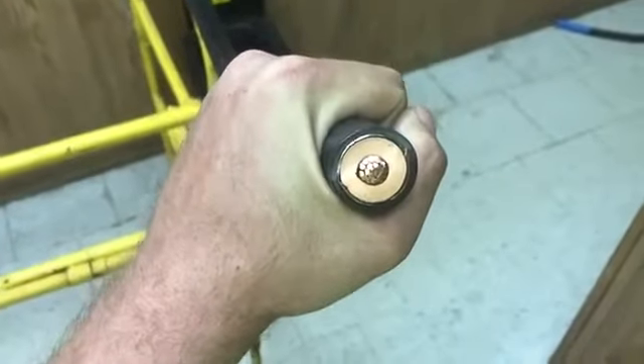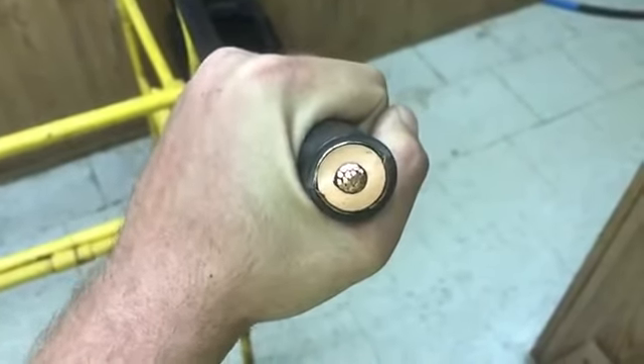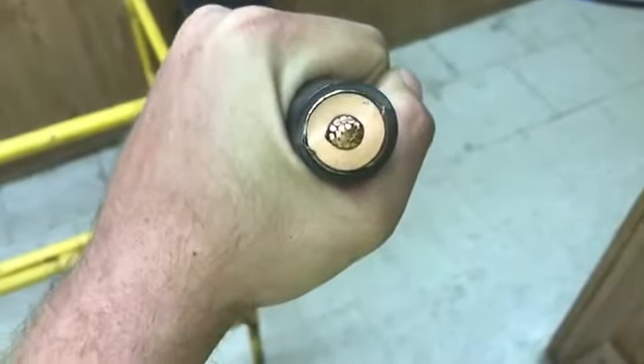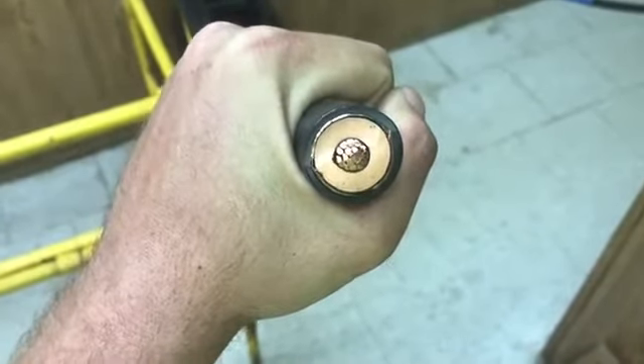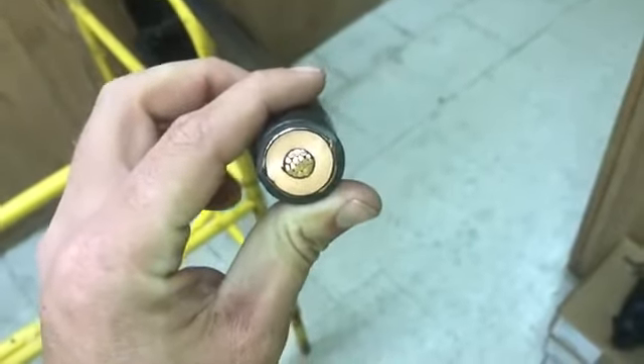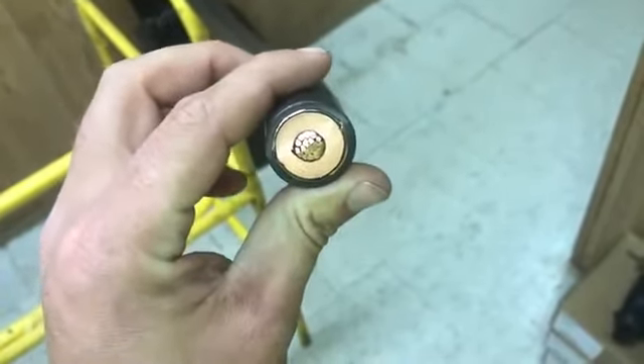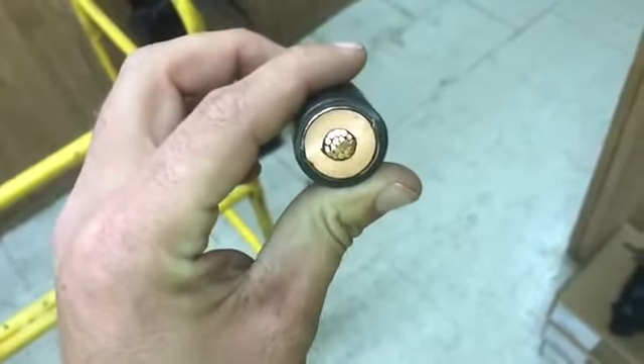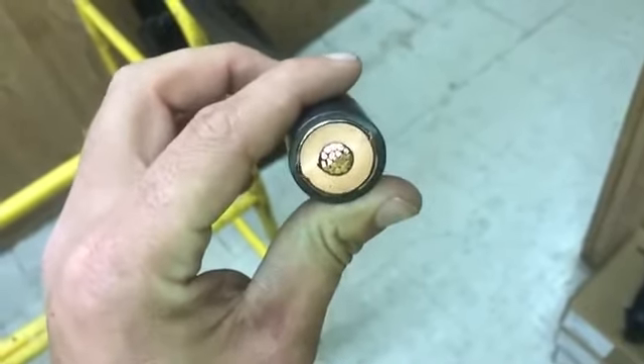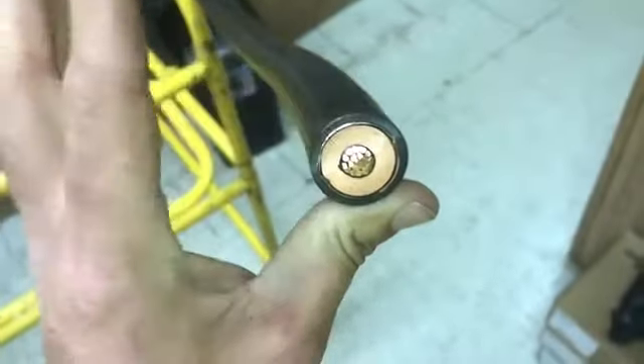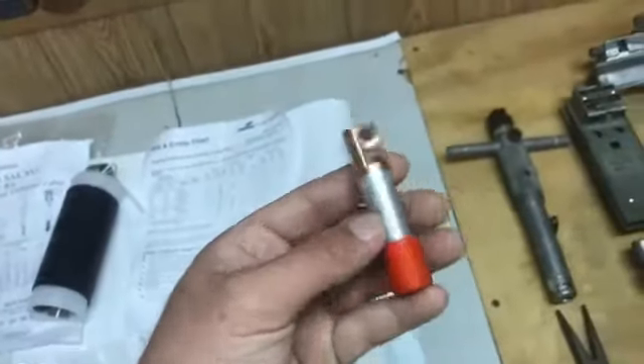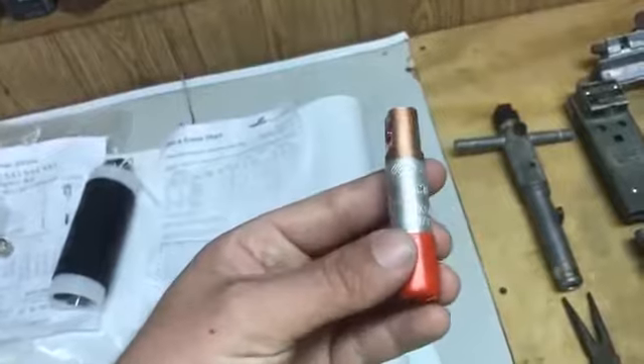This is the cable we're going to be using. This is actually a 1-aught compact copper EPR, or ethylene propylene rubber, copper tape shield cable. The cable itself is one size smaller than what it actually is. So if I say it's a 1-aught compact, it's actually the same size as a number 1 compressed cable. So all your terminations, like this copper top for instance, this isn't a 1-aught copper top, but it's actually a number 1 stranded copper top.